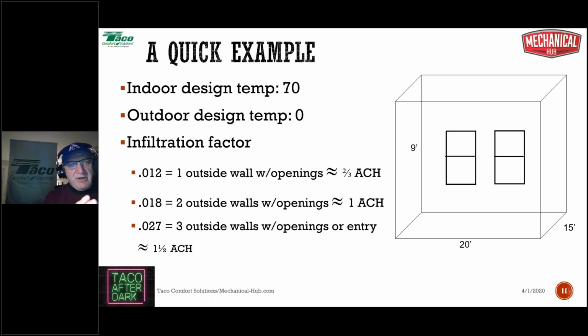I would use a number of 0.012, and what that represents is 2/3 of an air change per hour. Two outside walls with openings reflects one air change per hour, and the number we're going to use there is 0.018. Three outside walls with openings, or the main entryway of the house, is 1.5 air changes per hour, and we're going to use 0.027. Now, what do these numbers mean and where do they come from?